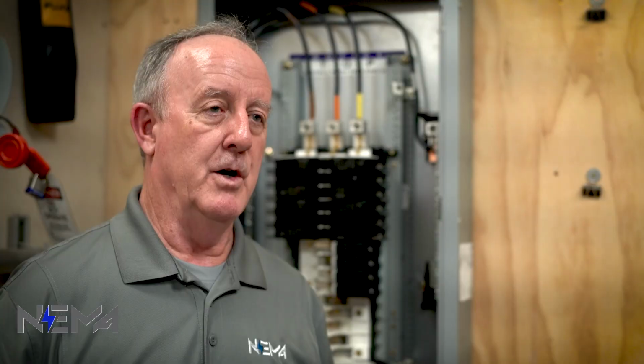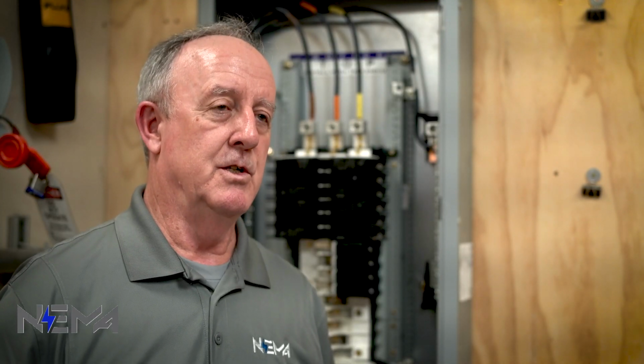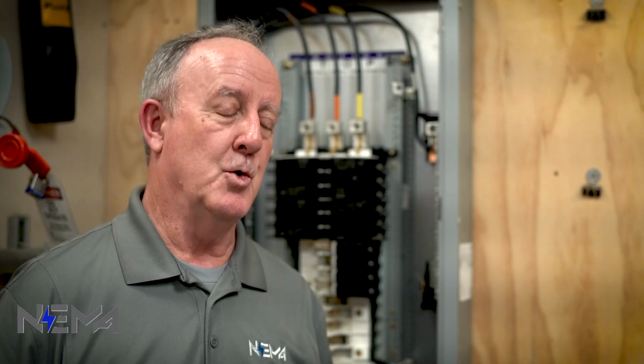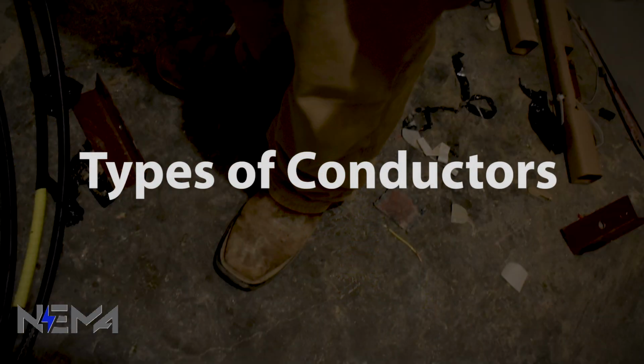Torque references first appeared in the 1975 NEC, and it required that manufacturer's instructions be followed for torque values. Then there was a new section added in the 2017 NEC in 110.14(D) that required that approved methods be followed to comply with the manufacturer's torque values on their equipment.